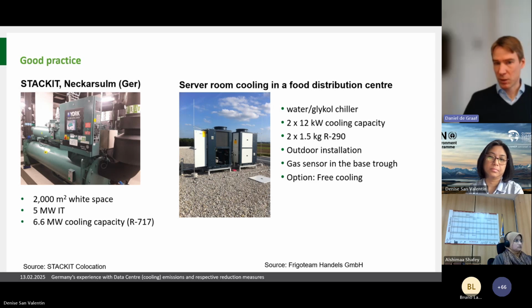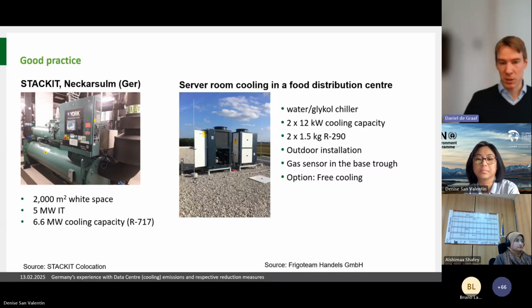For a very small data center on the right-hand side, I would even call it a server room, it's cooled with 2 times 12 kilowatts of cooling with an R290 cooling plant. As you can see, it's an outdoor installation, but equipped with a gas sensor in case of a leak, and you have the option there for free cooling, so you don't need a compressor and can save a lot of energy.